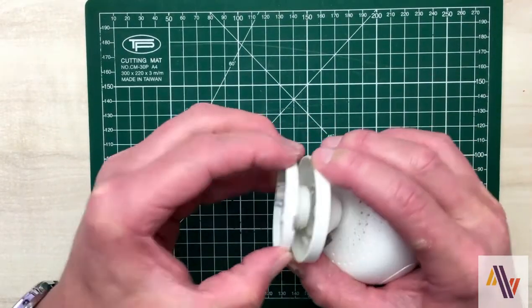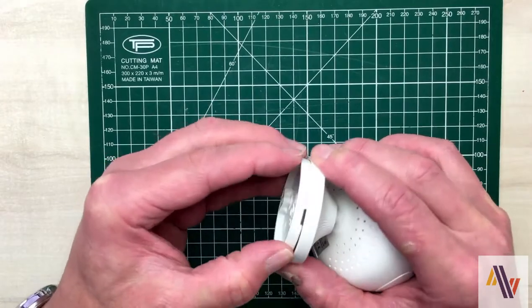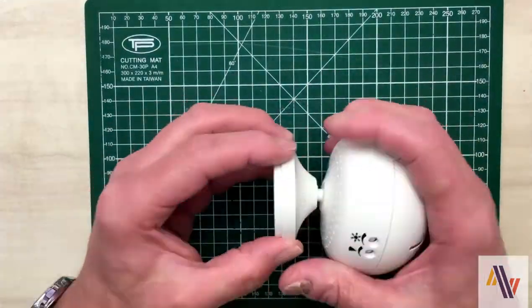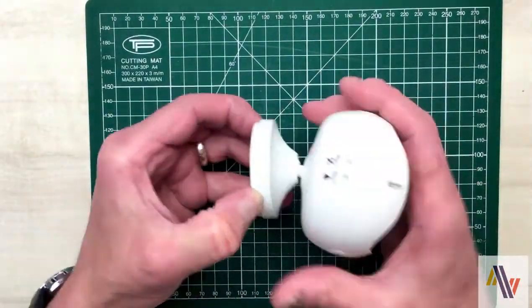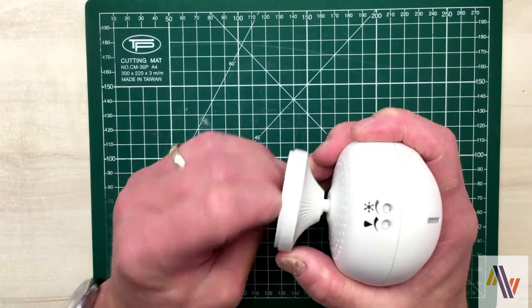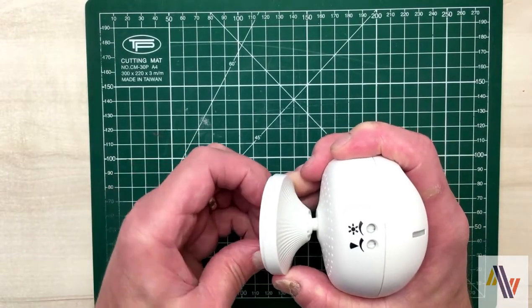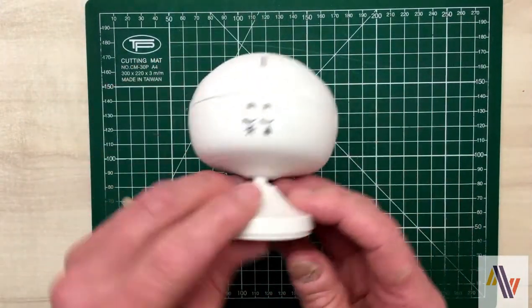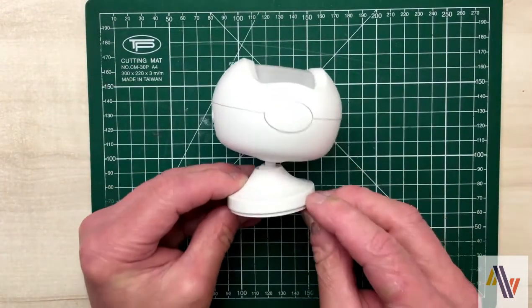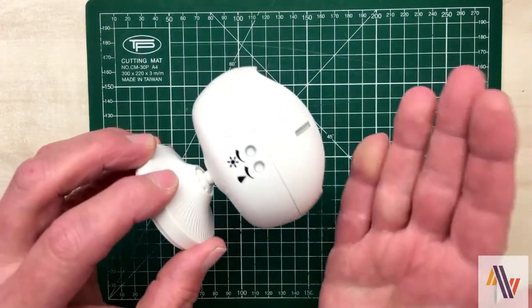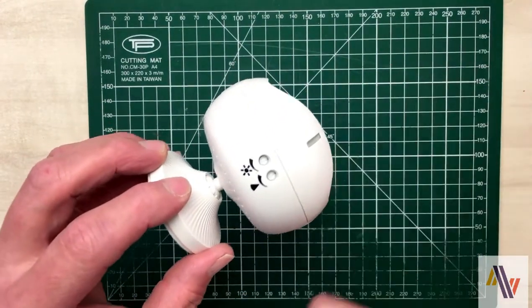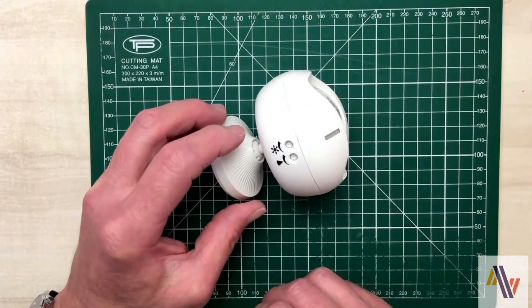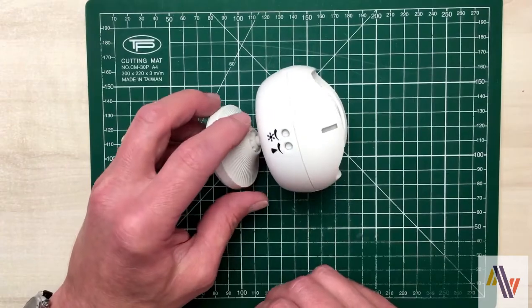Once the plate has been attached to the wall we reattach the sensor to the plate, tightening it up and ensuring that the sensor is pointing into the room. Bearing in mind that the PIR sensor detects movement across it rather than towards and away from it.